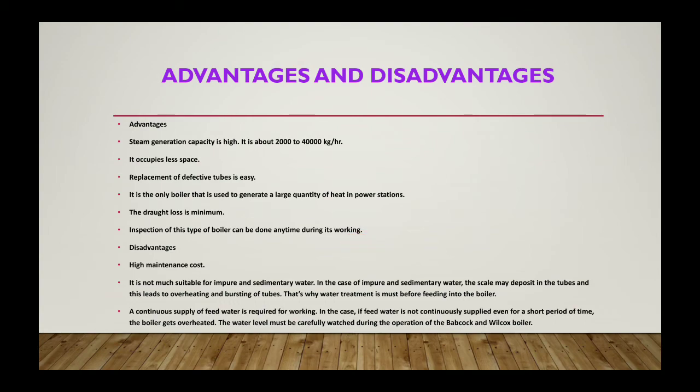And the disadvantages: it has a high maintenance cost. It is not very suitable for impure and sedimentary water. In the case of impure and sedimentary water, scale may deposit in the tubes, and this leads to overheating and bursting of tubes. That's why water treatment is a must before feeding the water.